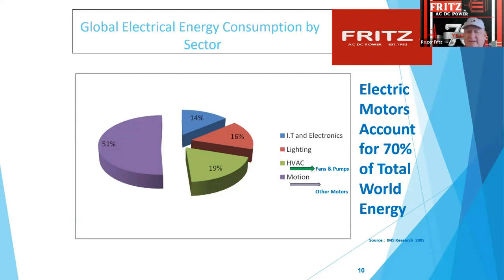A big focus was on buildings, putting on fans and pumps, but they tend to walk away from the motion side because the motors are in the critical process. It's hard to get engineering to accept this, so they tend to say, oh, well, it's a constant torque load, you can't do much. That's really not the case. We've proven that over and over again.